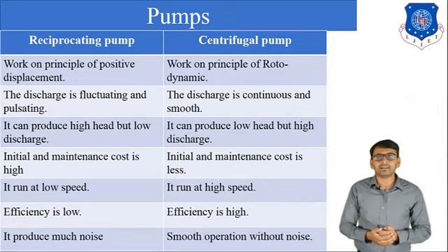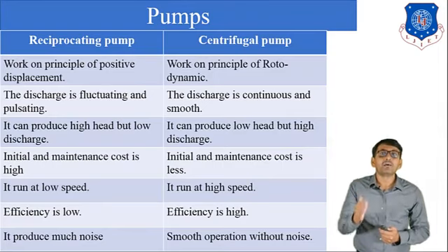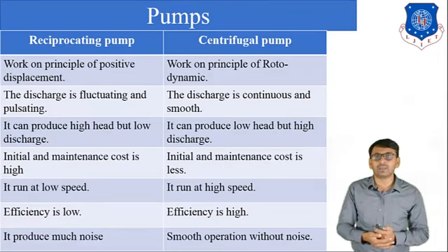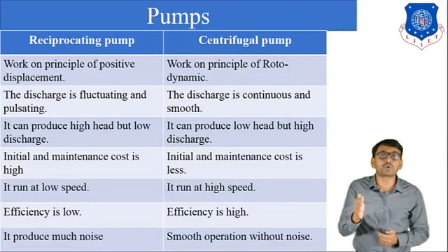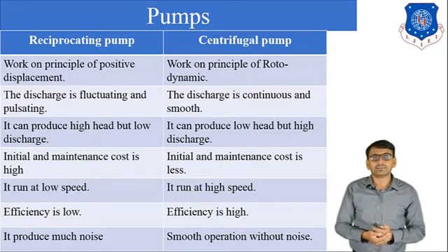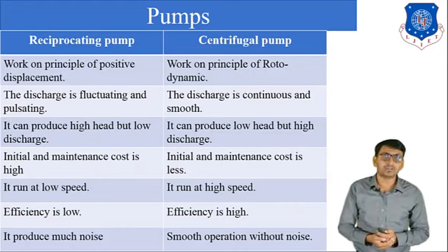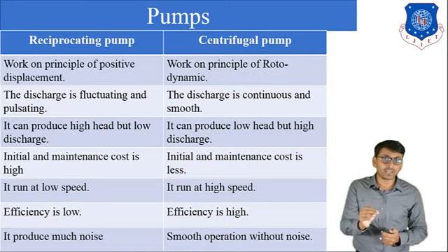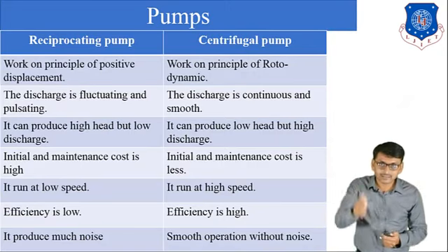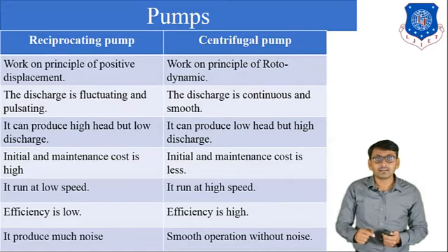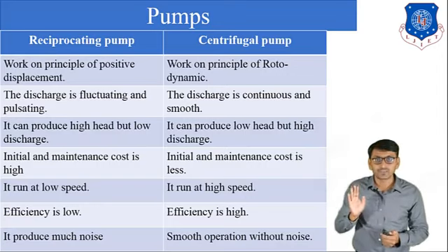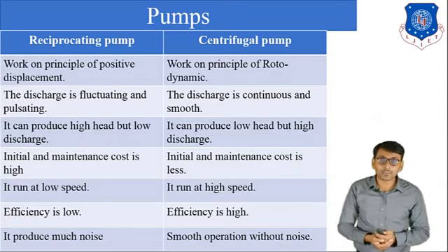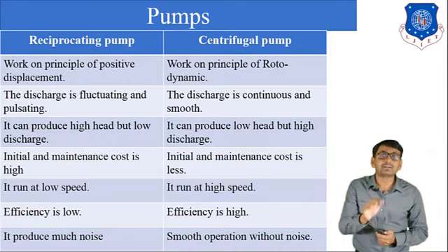So first comparison, the reciprocating pump works on the principle of positive displacement, and the centrifugal pump works on the principle of rotodynamics. Second comparison, in the reciprocating pump, the discharge is fluctuating and pulsating like this. But the discharge in the centrifugal pump is continuous and smooth. Third comparison, it can produce high head but low discharge.